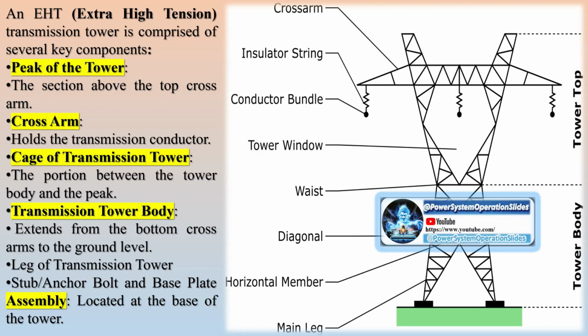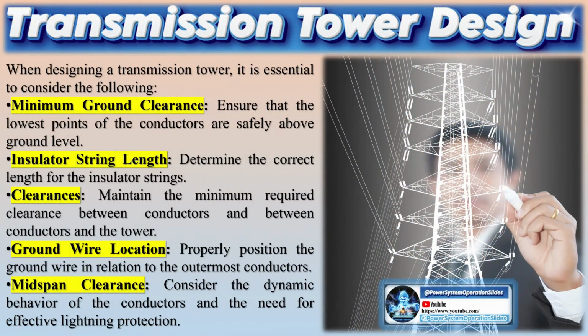At the top of a transmission tower, 1 or 2 smaller, solitary wires, known as overhead ground wires, static wires, or pilot wires, can be observed. These wires serve the purpose of absorbing or deflecting lightning strikes, safely conducting electricity to the ground. Under normal conditions, the voltage potential of these wires is 0, meaning they do not carry electricity. Some overhead ground wires are integrated with fiber optic cables that transmit telecommunication data. Fiber optic cables, made of glass, do not conduct electricity and are unaffected by lightning strikes.